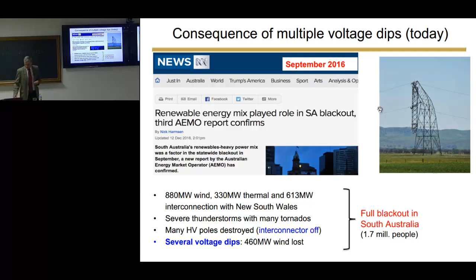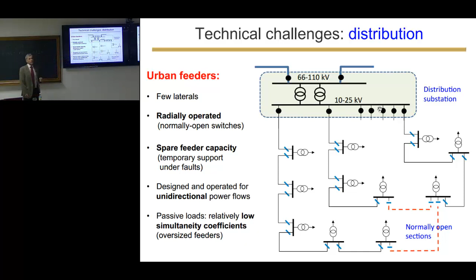Okay, let's move to the distribution side, since I'm probably getting late. Distribution systems are quite different. This is a summary of distribution systems: they are radially operated. We have normally open sections that can be useful for giving service via alternative routes in case of a fault, feeding a feeder from a secondary substation from another side. So this is the typical topology. They are designed for power flow from the substation to the load, unidirectional power flow, and usually the simultaneity coefficient is rather low, probably less than 0.5 or 0.3, something like this.